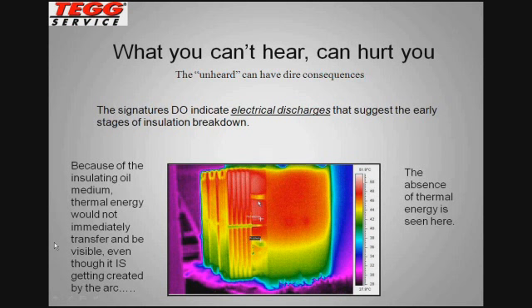Yes, actually, I was just getting ready to tie that together, so it is great timing on the question. I thank the person who put that in. If you look at this screen, traditionally, and I'm going to narrow this down to a liquid-filled transformer, you have a medium inside the transformer. The area of interest is going to be the windings, the winding insulation, and the terminations within that particular unit. The insulating oil is a cooling medium, and if you have anomalies like arcing occurring, there is a high volume of thermal energy or heat produced with the arcs. The challenge with infrared is that you need to change the temperature of that insulating oil dramatically before the infrared camera would be able to determine that this was occurring inside.